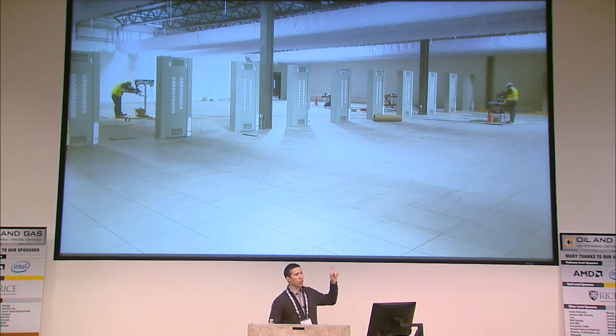Each one of these boards is a 1-megawatt panel board. It operates an entire row of tanks. And we run 70-amp three-phase all the way to the tank, which means we just get away with about half as many of these as we would otherwise have.